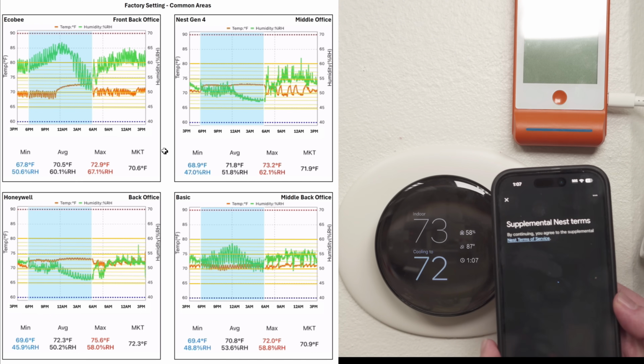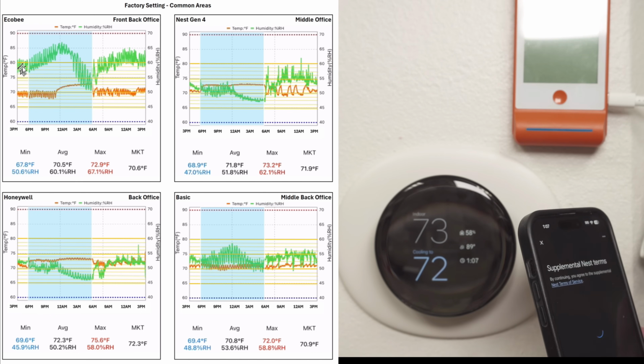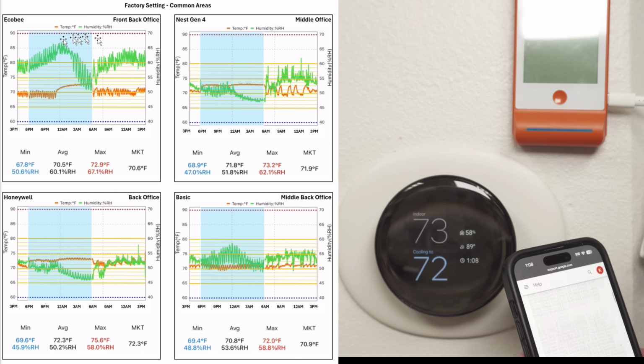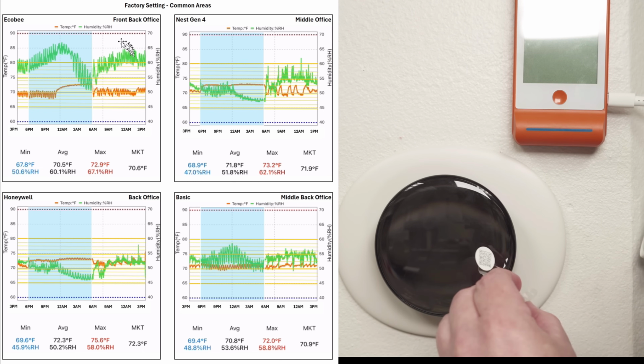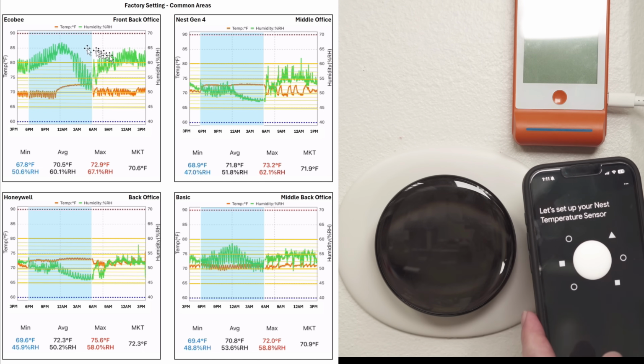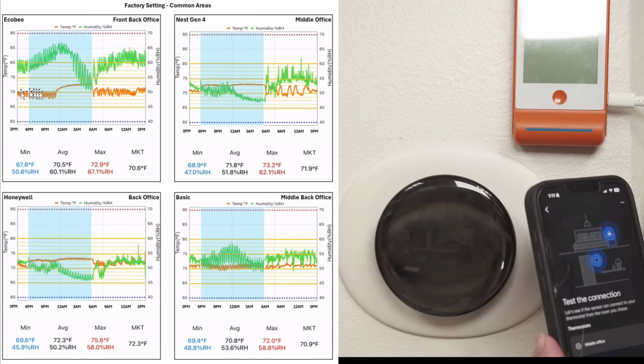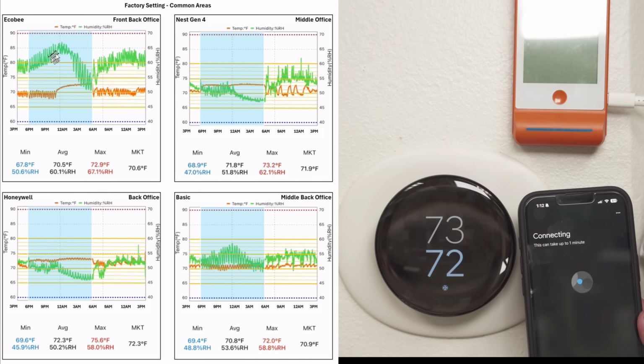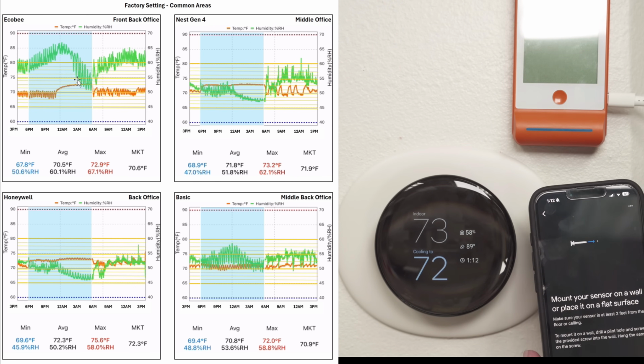As a side note, going back to the front office, these green lines representing humidity are too high, since anything above 60% humidity is considered uncomfortable. What's interesting is that as the unit runs, humidity levels go up, and when it's off, humidity levels drop.